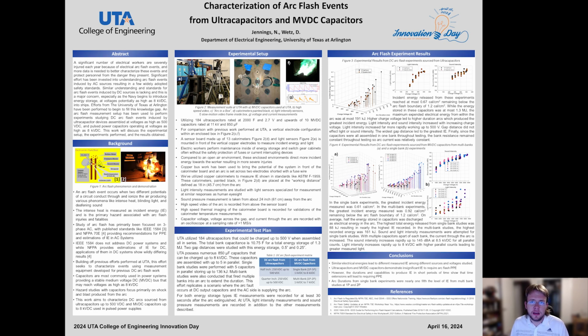Light intensity measurements are conducted with a light diode able to replicate light intensity measurements for a human eye. The intensity of the arc flashes is much greater than what a human eye would register, so we use neutral density filters to reduce the light to something the diode can see, then step that back up to the actual peak light produced within each arc.